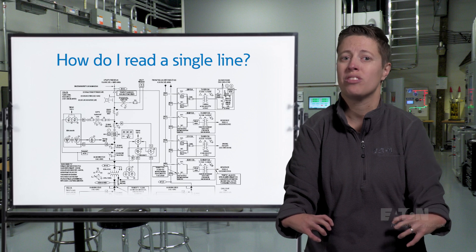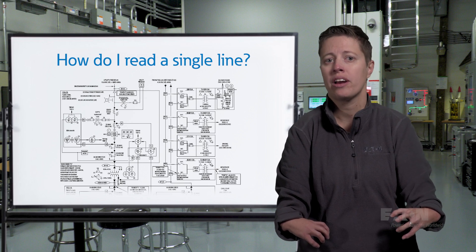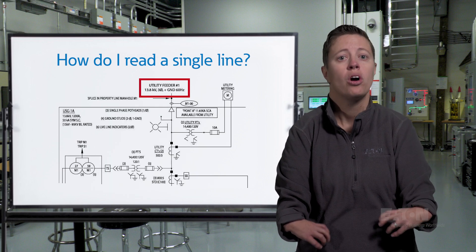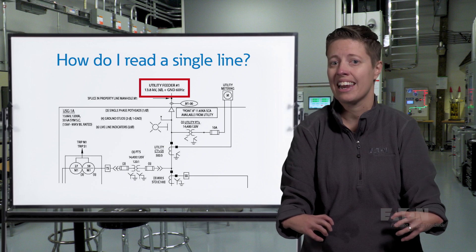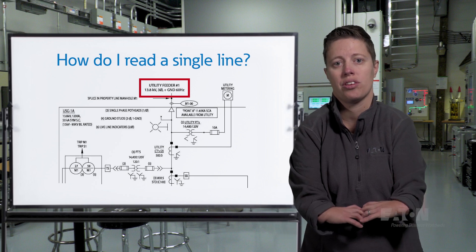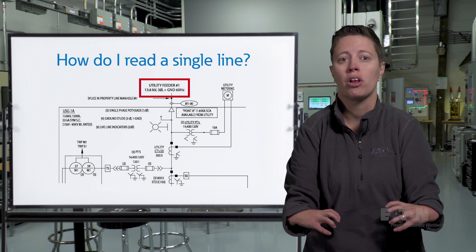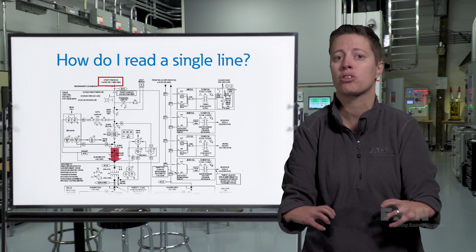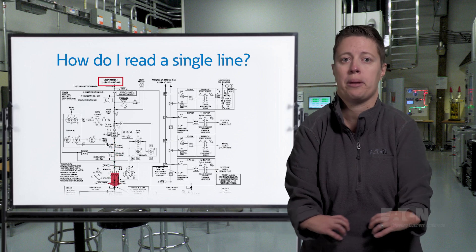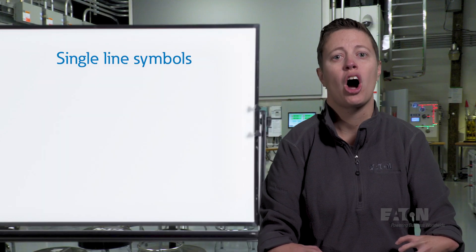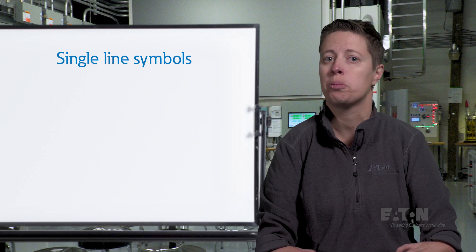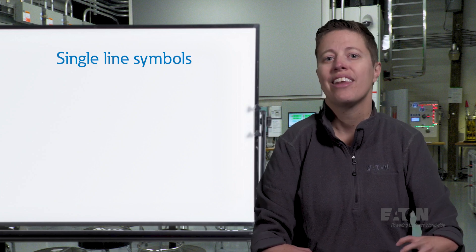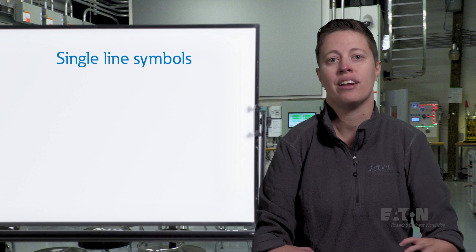A single line drawing is typically read from top to bottom or left to right. If the system is fed by utility power, look for a downward arrow, utility transformer, or reference to a utility connection to signal the start of the system. From there, you can follow the lines downstream to the loads, likely passing through several pieces of electrical distribution equipment along the way. There are dozens of symbols that are commonly found in electrical distribution single line drawings. Let's start with the basics and then look at an example system.